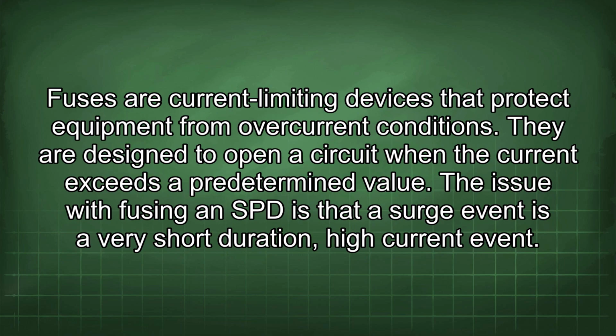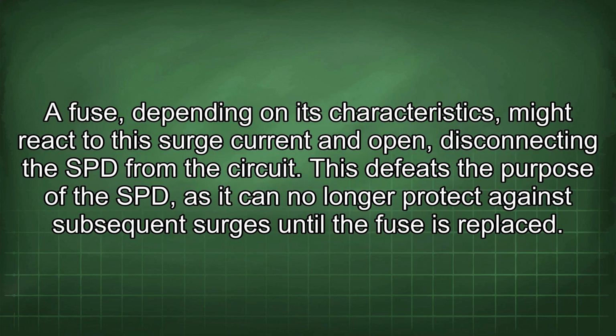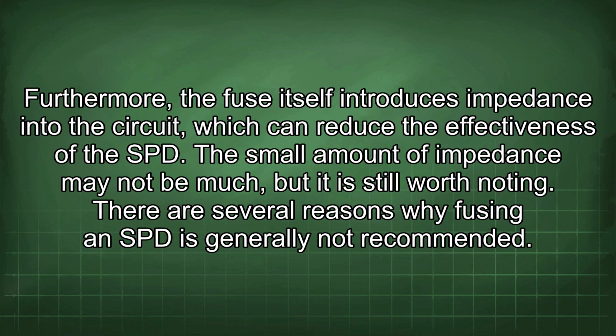Fuses are current-limiting devices that protect equipment from overcurrent conditions. They are designed to open a circuit when the current exceeds a predetermined value. The issue with fusing an SPD is that a surge event is a very short duration, high current event. A fuse, depending on its characteristics, might react to the surge current and open, disconnecting the SPD from the circuit. This defeats the purpose of the SPD, as it can no longer protect against subsequent surges until the fuse is replaced. Furthermore, the fuse itself introduces impedance into the circuit, which can reduce the effectiveness of the SPD. The small amount of impedance may not be much, but it is still worth noting.